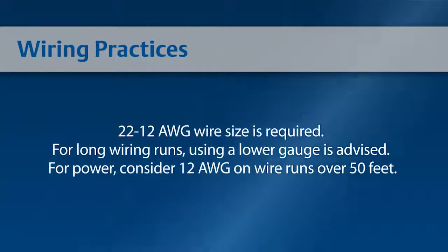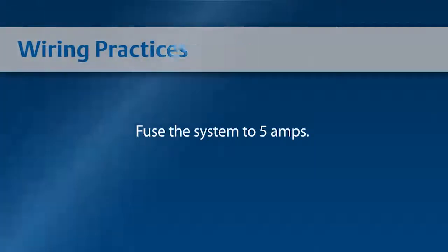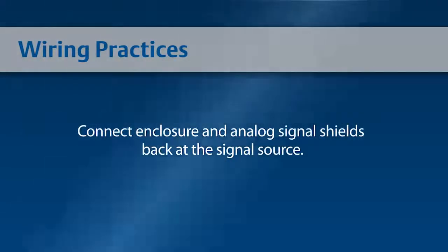22 to 12 gauge wire size is required. For long wiring runs, using lower gauge wire is advised. For power, any wire over 50 feet should be 12 gauge. The actuator will demand no more than 4 amps. Therefore, fuse the system to 5 amps. Using shielded wire for both power and signal, connect power and analog signal shields back at the signal source.